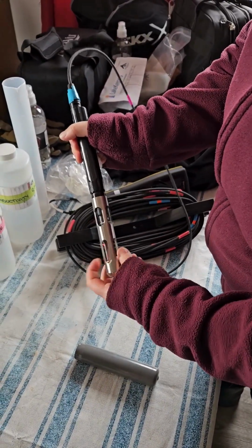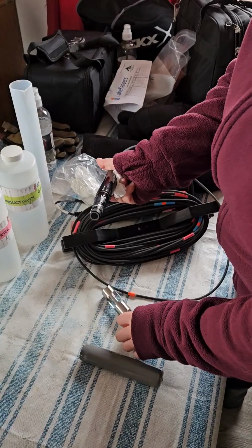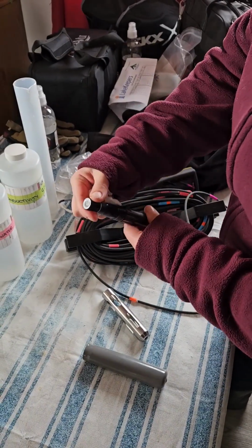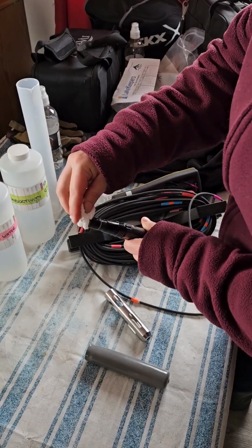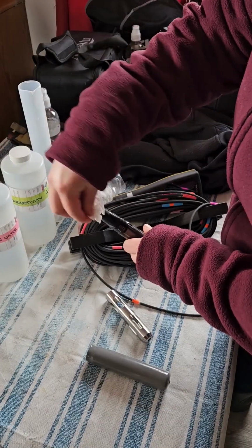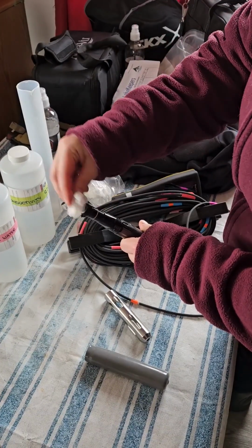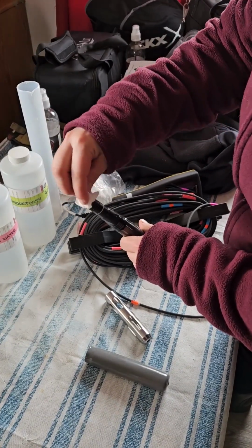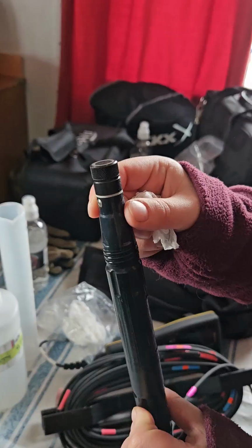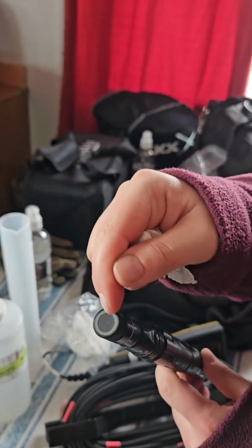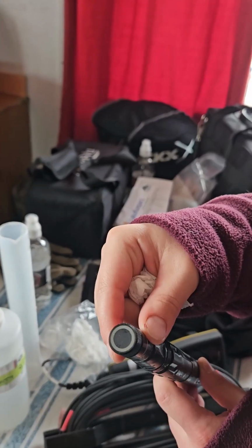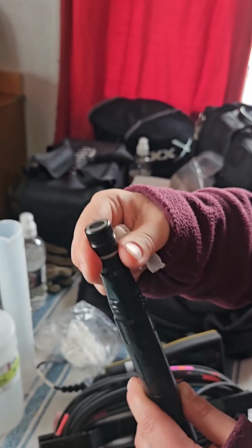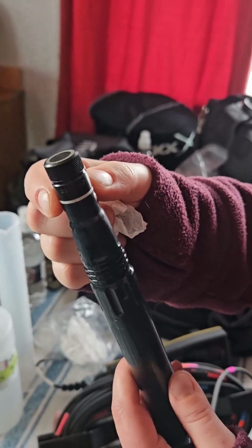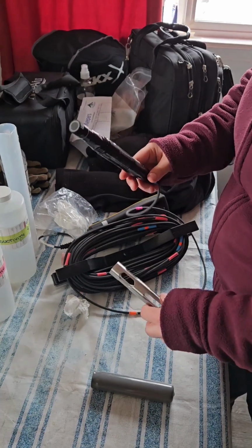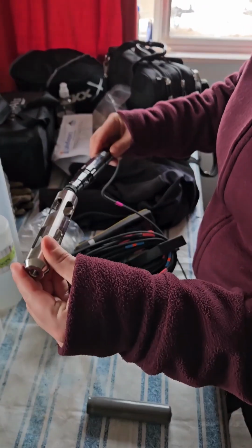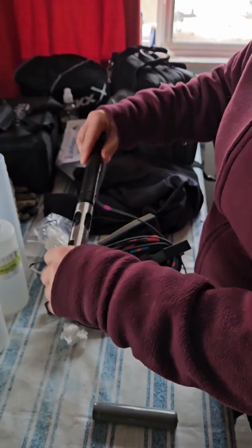Be careful when you are removing it that you don't nick the end of the probe or hit the sensors. And we will take a Kim wipe that's in your kit and dab the probe tip on and around, just making sure there's no moisture. And then we will inspect the probe sensor to make sure that there's no nicks or bumps or anything like that. Once we've inspected it, we can put the metal guard back on carefully and screw it back on till it's tight.